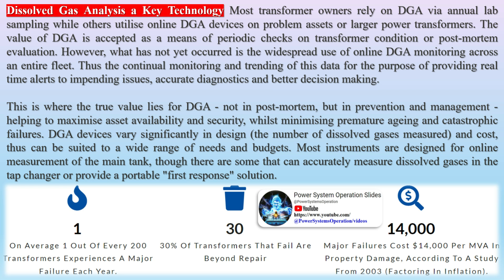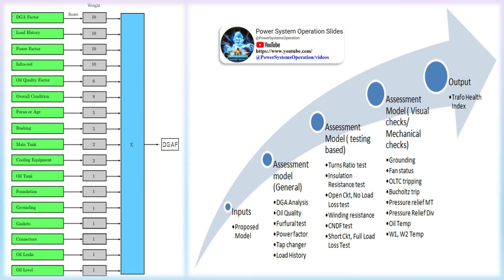DGA devices vary significantly in design, the number of dissolved gases measured, and cost, and thus can be suited to a wide range of needs and budgets. Most instruments are designed for online measurement of the main tank, though there are some that can accurately measure dissolved gases in the tap changer or provide a portable first response solution.